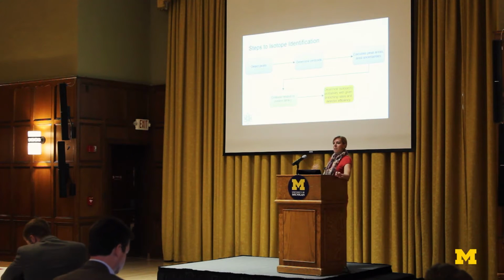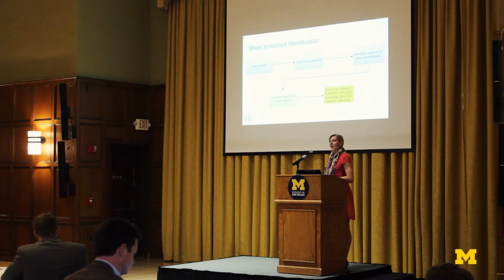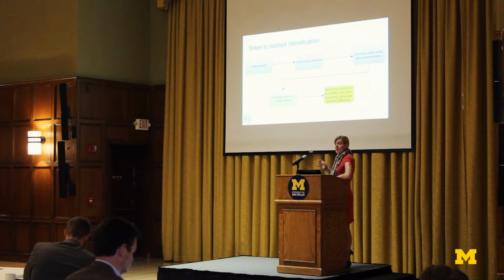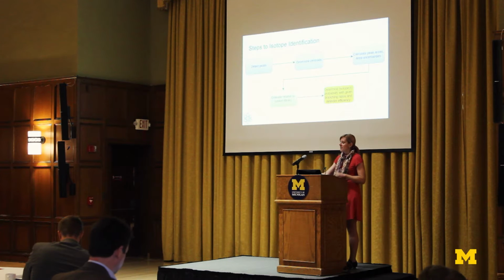Okay, so this is sharing my philosophy on isotope identification, and this differs from many other people, such as Dean Mitchell, who's kind of the godfather of the field. But having done the spectroscopy mission for the emergency response community, the way that I approached analyzing a spectrum is I first look at the peaks. And in looking at the peaks, that's giving me my unique fingerprint to the isotope that's present. So I have to determine the centroids of those peaks very accurately, and I want to know something about their areas, because those areas are going to make some sort of sense to me when I start looking at branching ratios and efficiencies of detectors and whatnot. So I want to know the areas, and I also need to know the uncertainty in those areas.